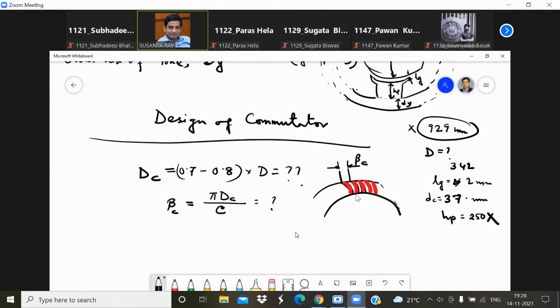So once this is complete, then you calculate the actual armature current, and that is the current that you have calculated earlier minus the field current. Okay, so if you have the armature current, then the brush current you have to calculate. The brush current is generally the armature current into 2 divided by number of poles. So the brush current you have to calculate like this.